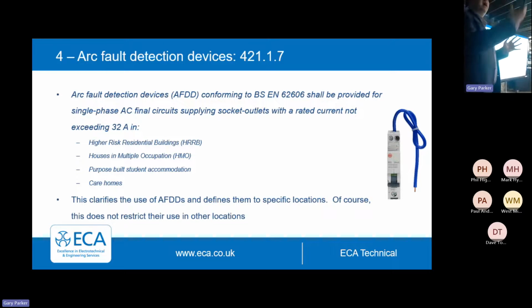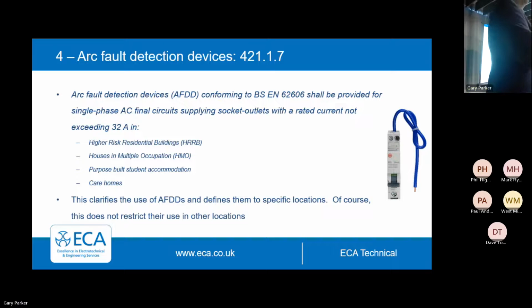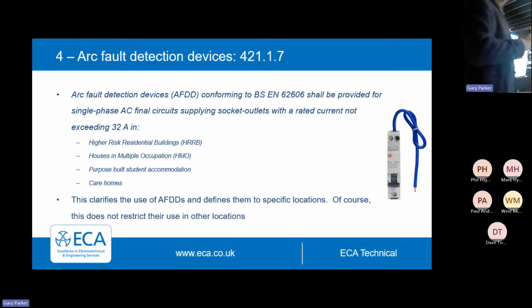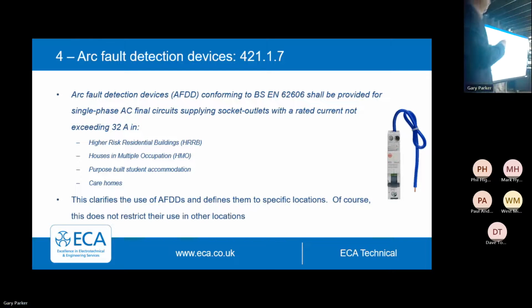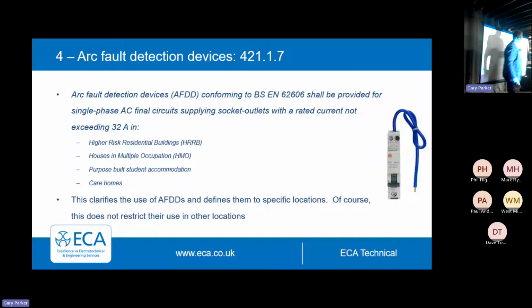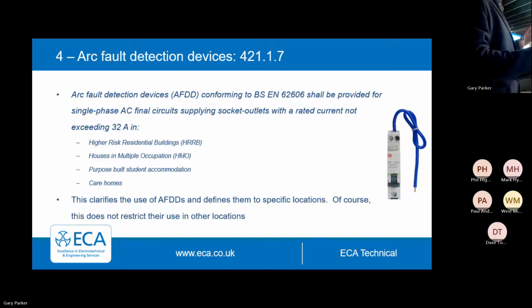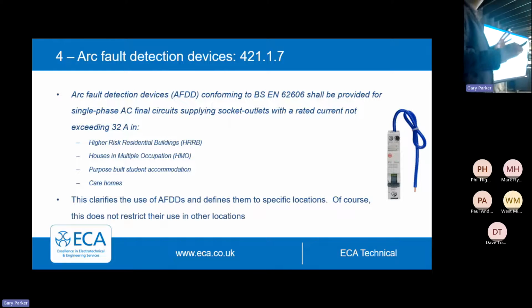Without that carbonated path, if you get XLPE or low smoke and zero halogen cable, if you burn it, it doesn't carbonize, it just turns into a gunk. That doesn't carbonize. There isn't a conductive path. So these devices won't necessarily work on cables that are XLPE. However, that's plugged into the socket. So these things won't work on XLPE cables, but they will work on PVC. So things that are plugged in. So from a specification, from a design point of view, just bear in mind, sometimes they're not really worth it, which is strange, isn't it?